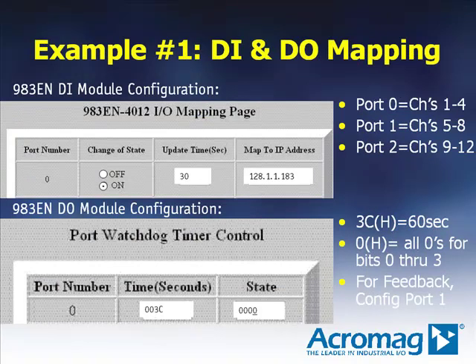From the top screen capture, you can see that we'll turn on change of state updates for port 0. We'll also program the timed updates for every 30 seconds, which will basically act as a heartbeat for the system. We'll map the four-channel port over to IP address 128.1.1.183. The bottom screen capture shows how we're configuring the watchdog timer and output states on the discrete output module. The watchdog timer is set to 3C hex, which corresponds to 60 seconds decimal. The output state is set to 0, which means all four output channels for port 0 will be de-energized if communications does not occur within 60 seconds. If the user was interested in looping back the status of the discrete output, they would simply wire the output to a channel on port 1 and set up I2O communications similarly going back to the input module.